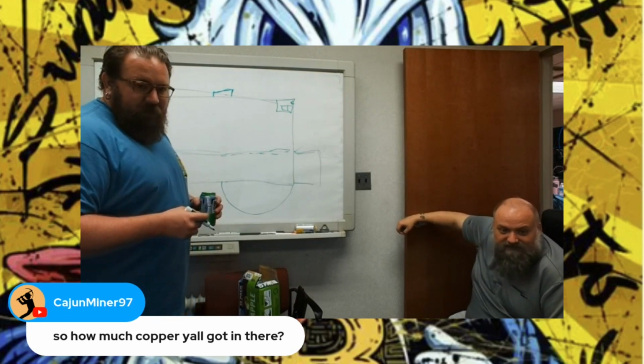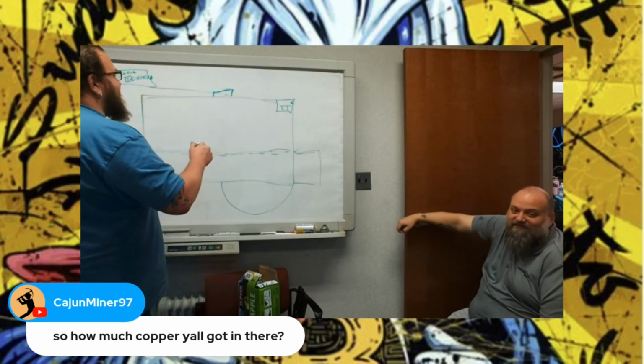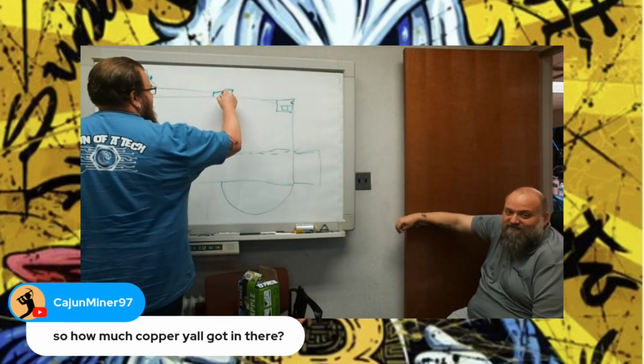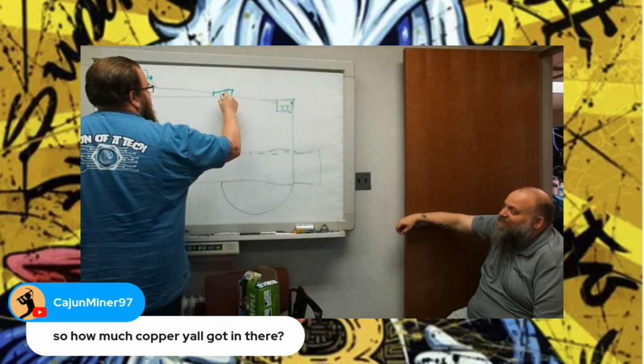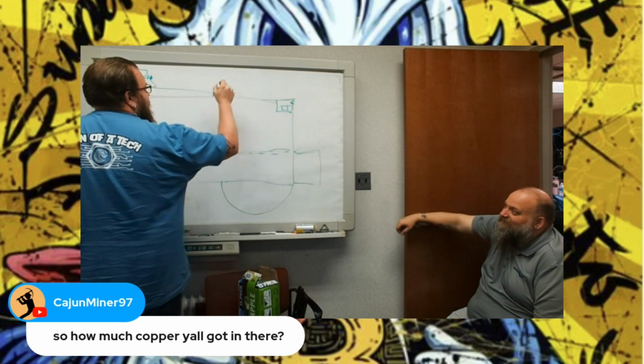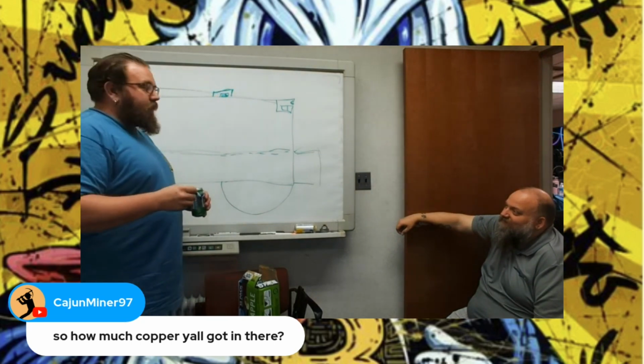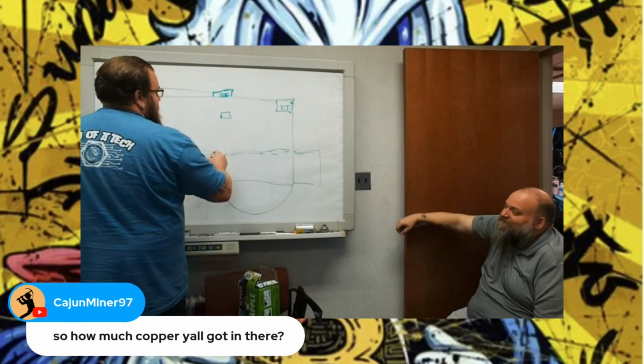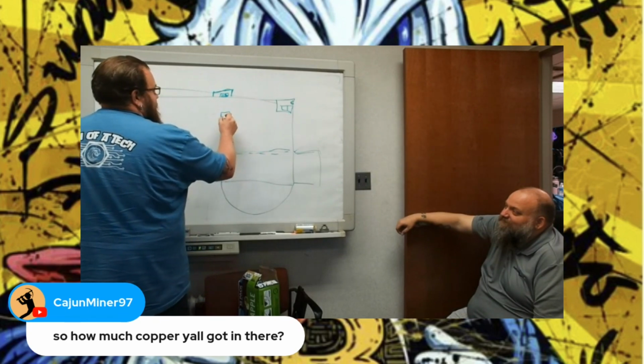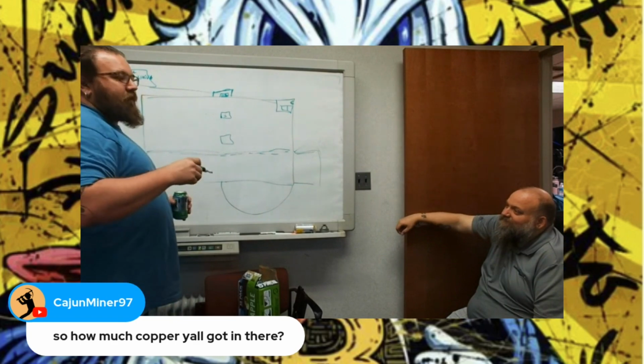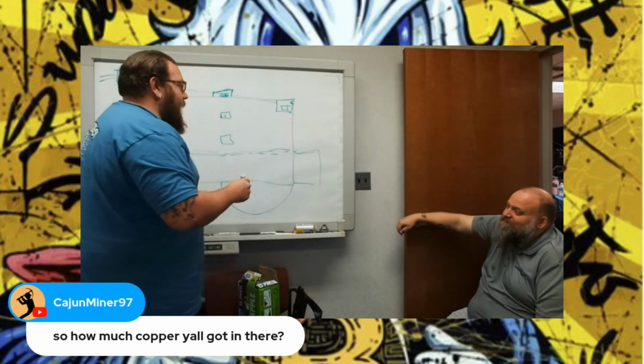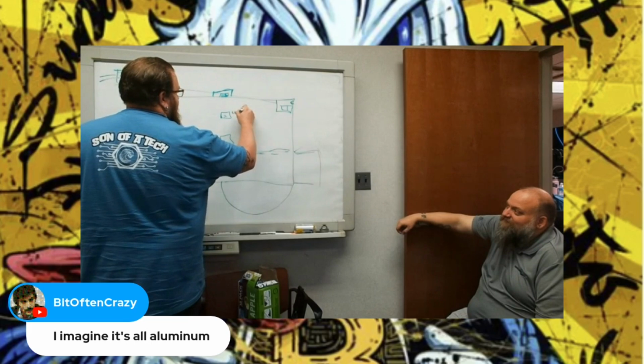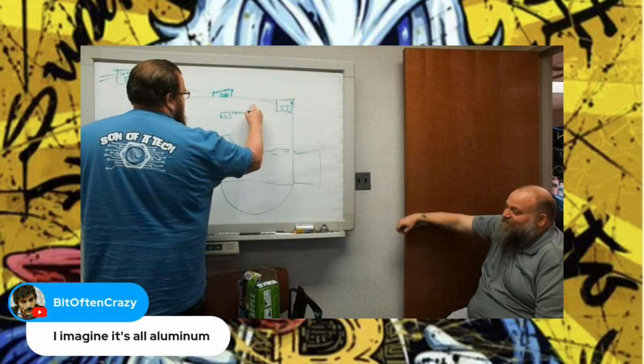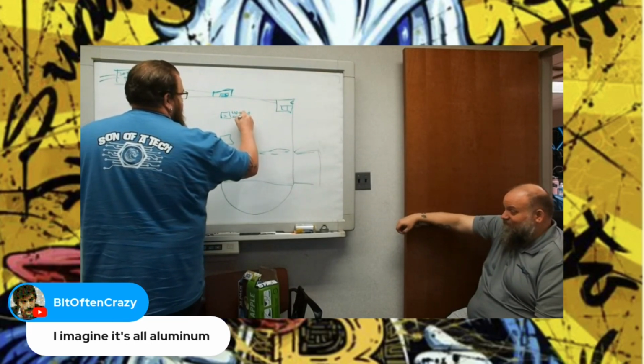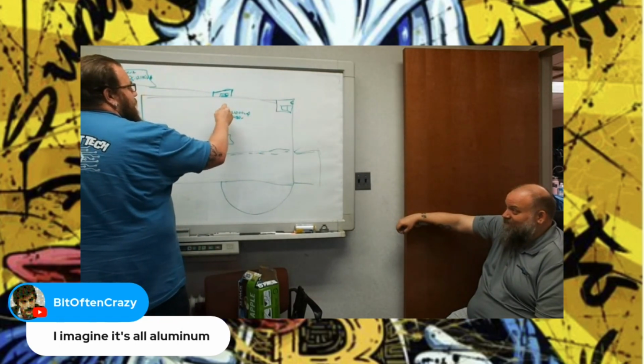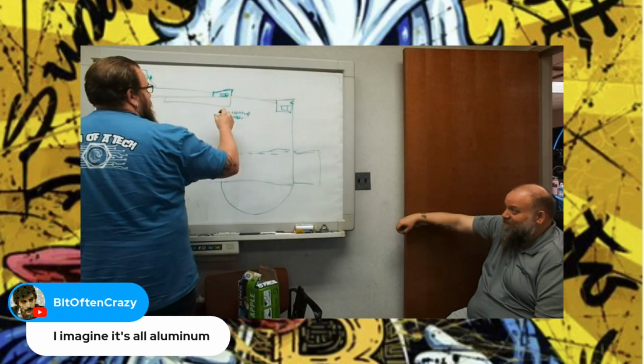So how much copper y'all got in there? Way too much. Yeah. This is a meth head's paradise. Don't come here. We'll shoot. So there is a 2.5 MVA transformer outside that feeds mezzanine 1. Mezzanine 1 has about 4,000 amps of power at 480. So again, that's 4,000 amps at 480. We take that 480, and that's where we start building out our wall.